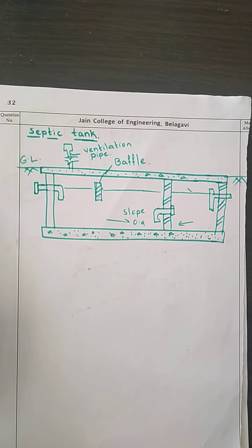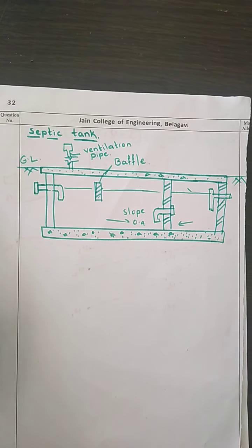The digested sludge is going to be withdrawn with a pipe of at least 15 centimeter diameter, under a hydrostatic pressure of around 45 centimeter. Nowadays very sophisticated instruments have come. If we apply a sucking pipe here, whatever waste we have, the sludge can be removed.